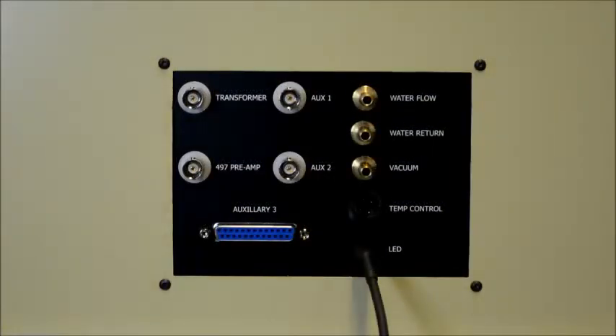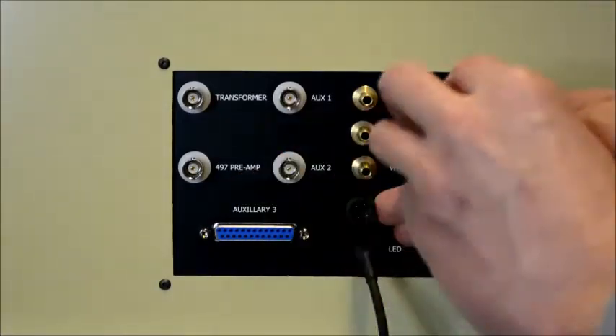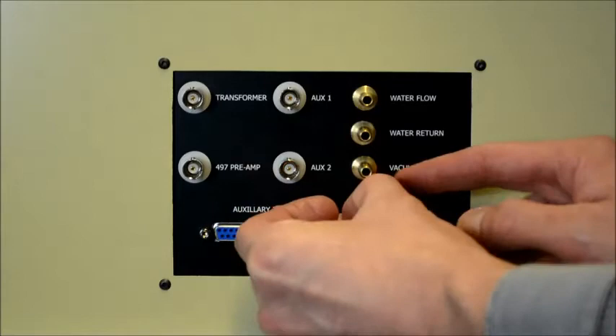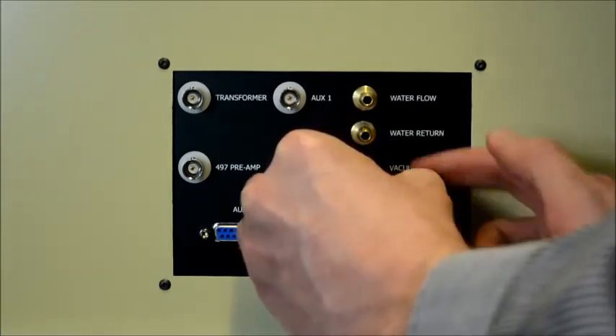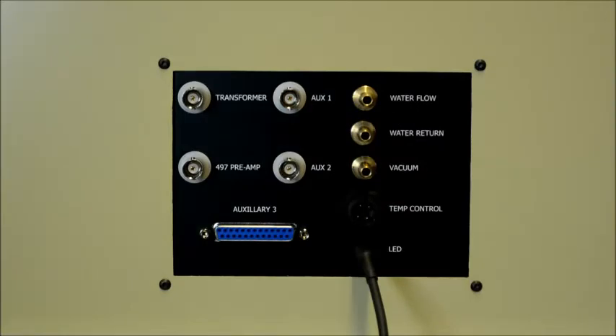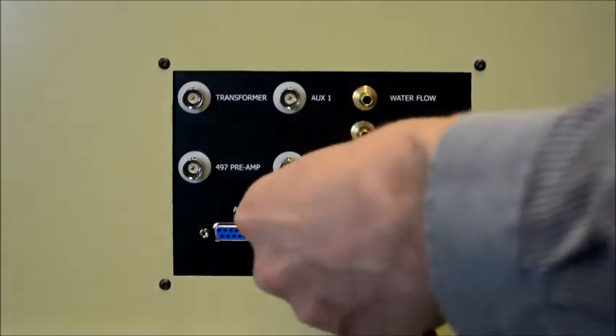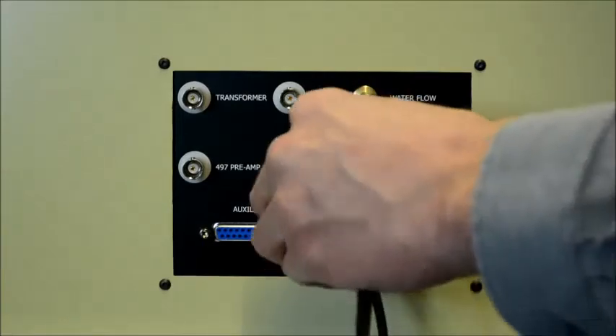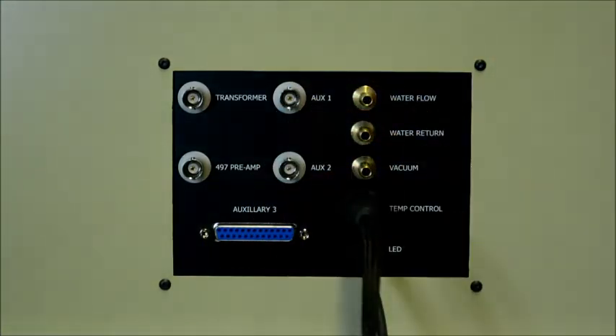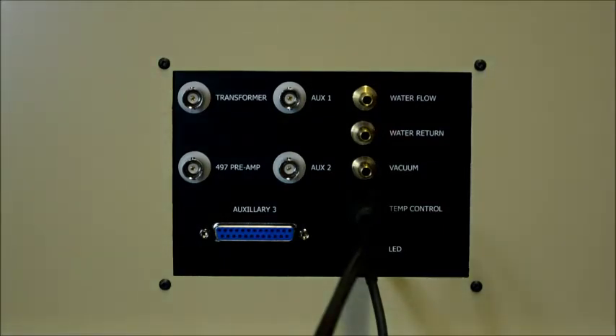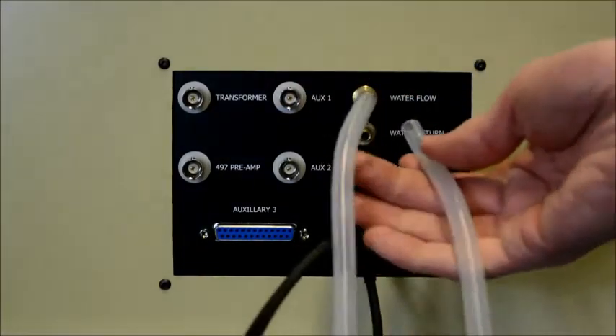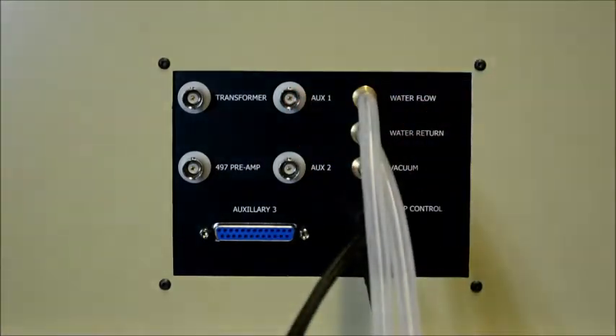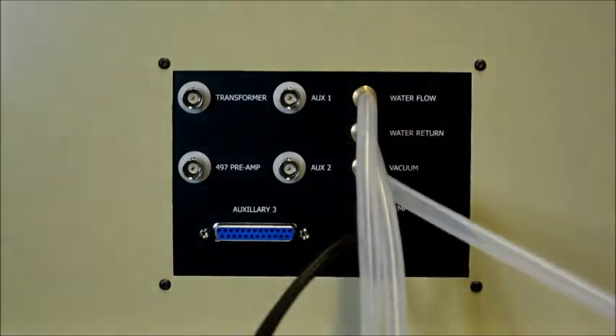Pass the lead of the temperature controlled vacuum chuck through the connection panel and hold in place using the retaining nut provided. And clearly this is a job for 2 people, 1 from the inside of the chamber and 1 from the outside. One can proceed to connect to the VC-TE20 using the 4-way cable, locating the pin and rotating the collar to lock in place. And one can also connect the longer silicon pipe provided to link the water flow to the VC-TE20 port of the same name, and similarly with water return and vacuum, making sure of course not to mix these inputs up.